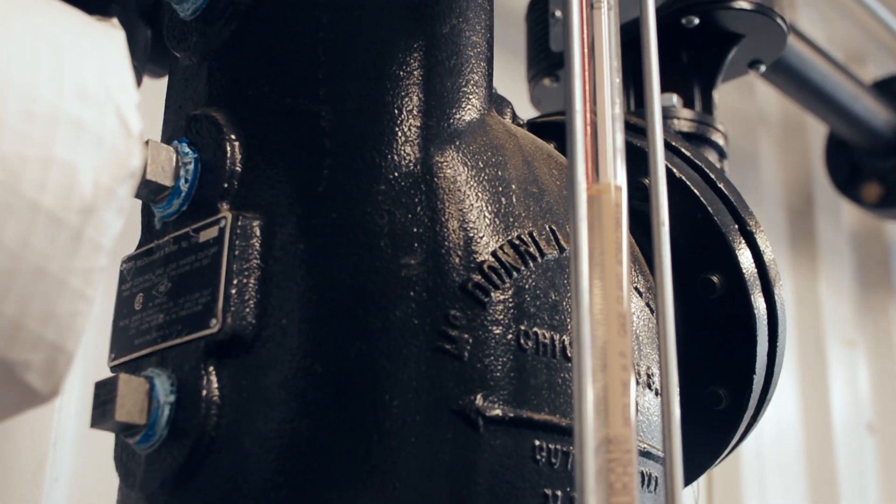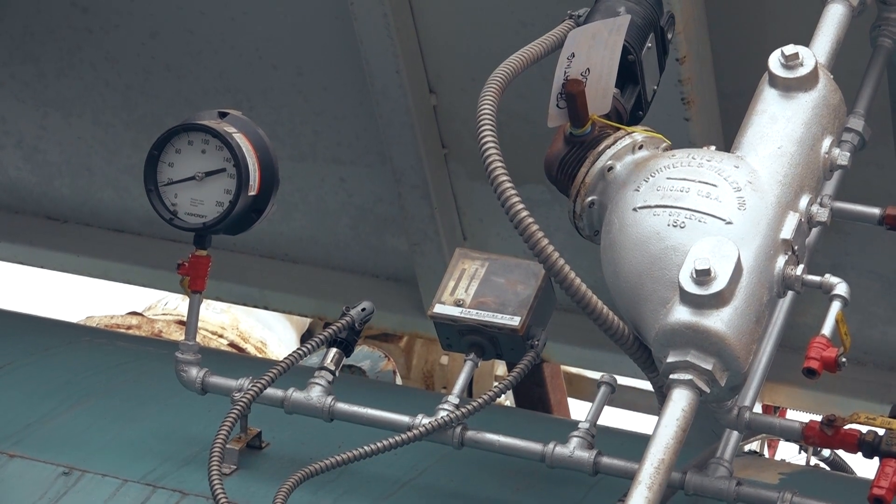This control is one of the most important controls and safeties found in the boiler room. The manufacturer recommends replacing the head mechanism every five years regardless of its functionality. Many plants will replace these controls even more frequently based on their in-house procedures. If you don't already have this control incorporated into your daily, weekly, monthly, and annual maintenance plans, then this should become an absolute top priority. Don't gamble with low water in a boiler — the results can be devastating. Stay safe out there.